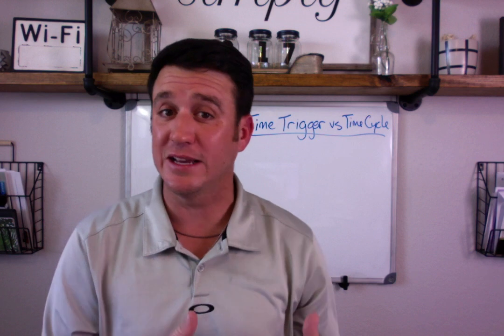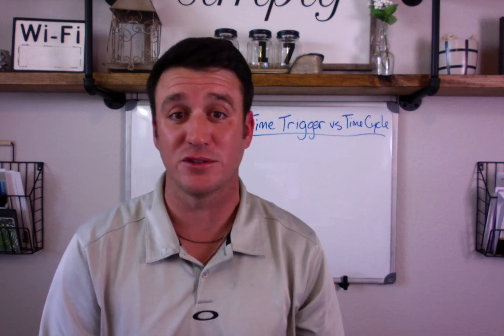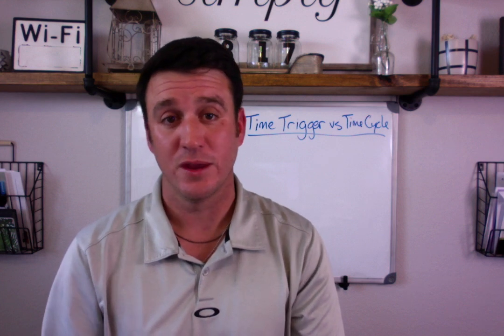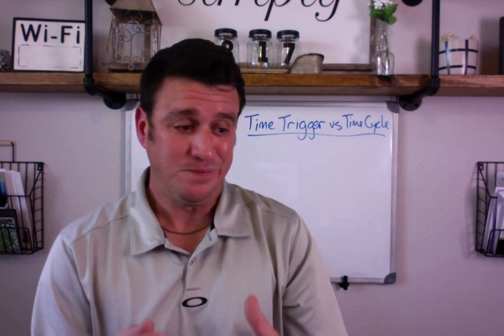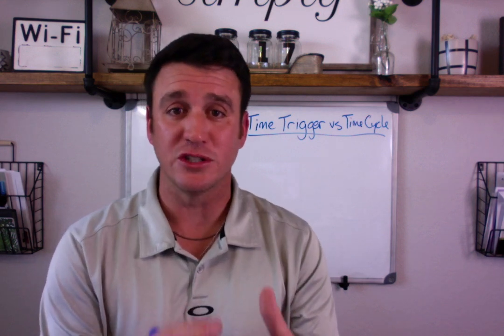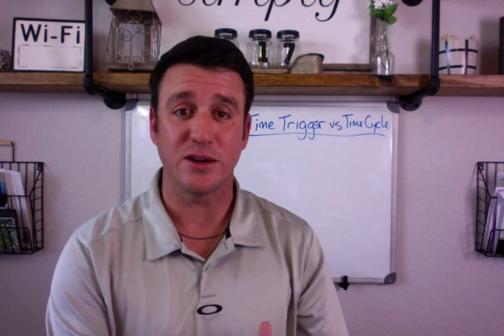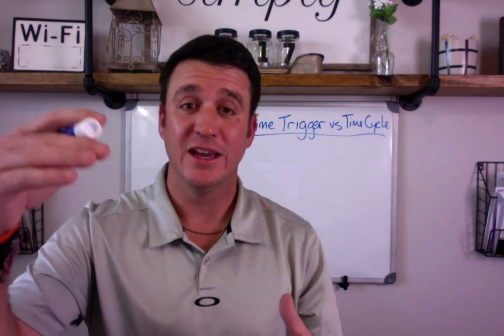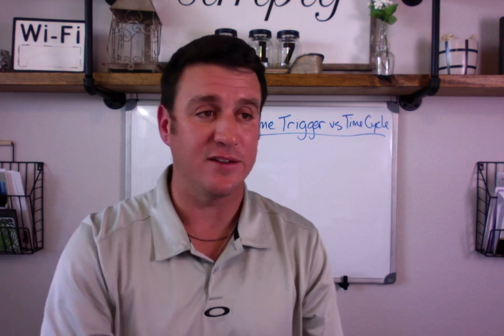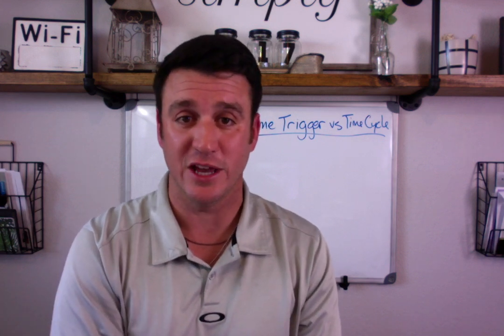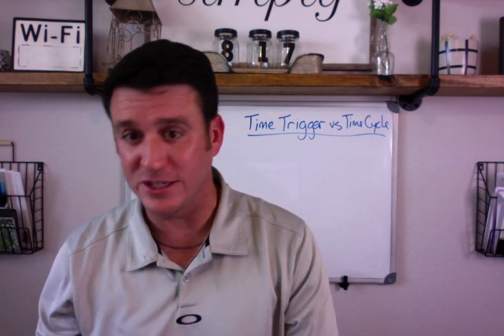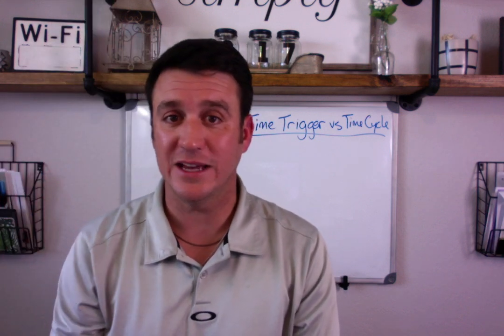When we talk about cycle, it gets a little more complicated because you have to ask yourself: am I in volume control or am I in pressure control? If you're in volume control, then your cycle is volume. The delivered breath is delivered — let's say you have a tidal volume of 400 milliliters set. The 400 milliliters is delivered, the vent cycles off, and exhalation happens. It's that simple.